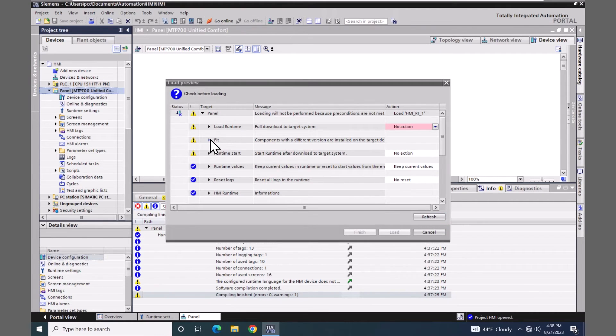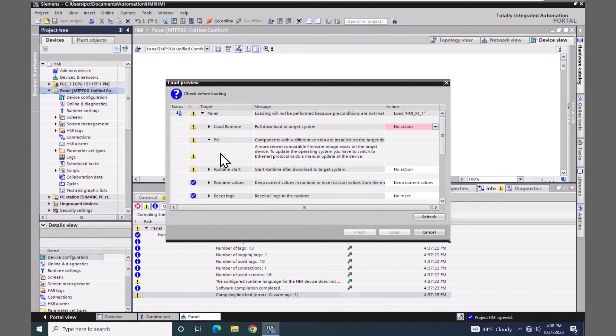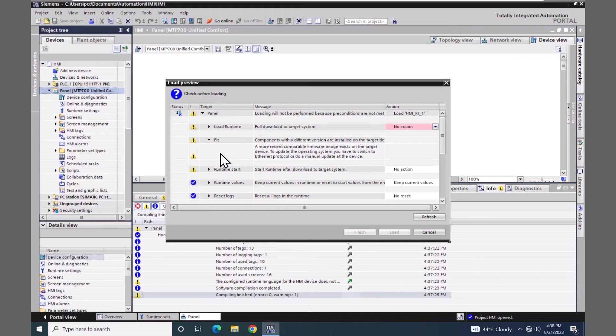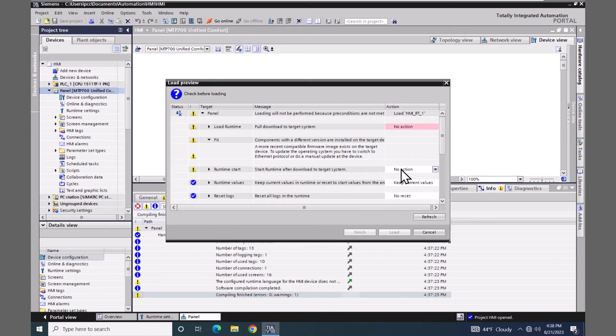And it actually brought up another entry here which is called FIT. This is showing that a more recent compatible firmware image exists on the target device. So I have an 18.0.0.2 image on my unified comfort panel. The version in my project is only version 18.0.0.1, so I can download my older device configuration into this compatible version. If it was an incompatible version then I would have the option to be able to update the operating system.